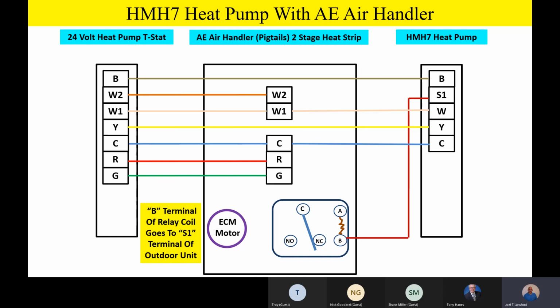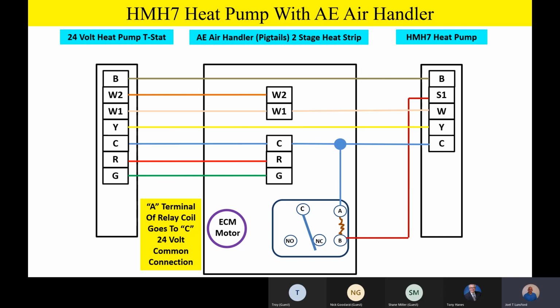You'll notice with the relay just sitting there unenergized, the contacts haven't moved. If we do not have an S1 signal, the relay is just sitting there in its unenergized state. The other side of that relay coil is going to go up to 24-volt common, which makes sense because it's a 24-volt AC coil on that relay. Now, the common terminal of the switching contacts, we're going to make up on the yellow wire so that anytime we're calling for compressor operation, we're going to energize the common terminal of the switching contacts.